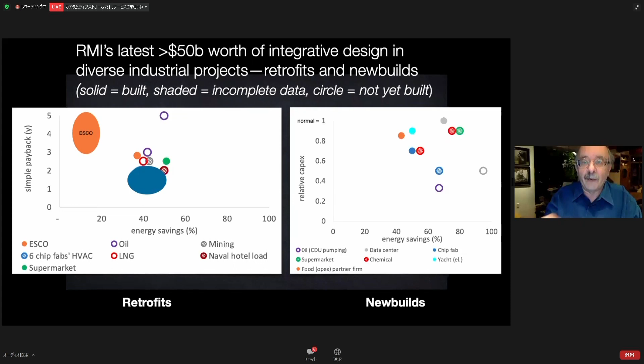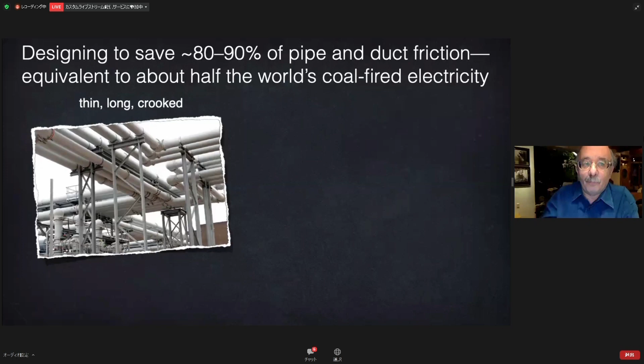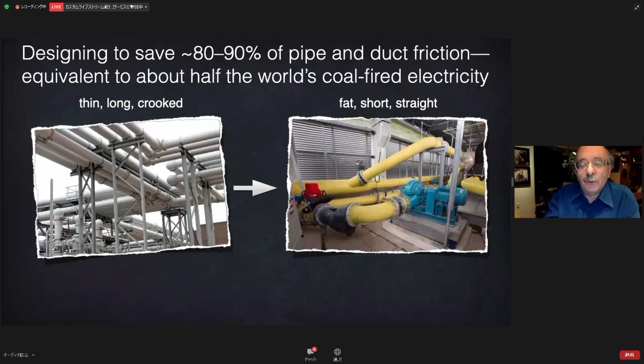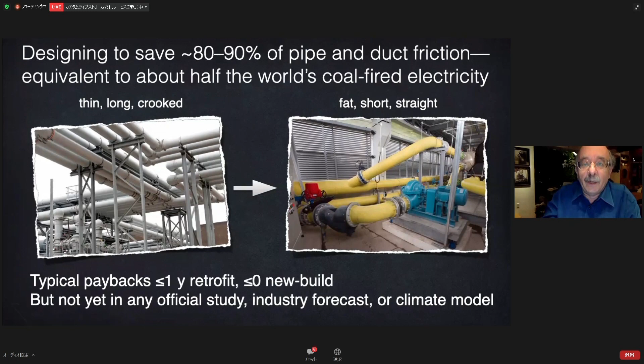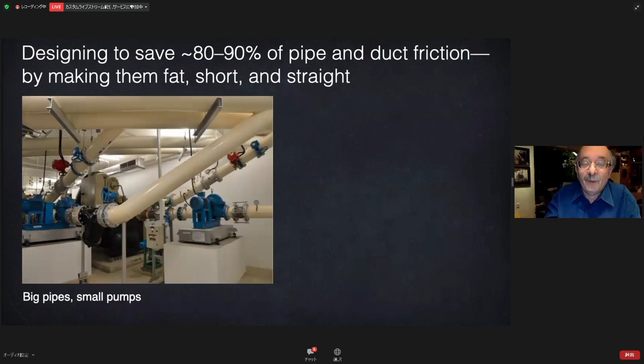Our better systems come from rethinking industrial processes and redesigning basic elements like pump, fan, and motor systems. For example, in both buildings and industry, better pipe and duct design can save about 80 or 90% of friction, 97% here in my house. If everyone did it, this could save roughly two-fifths of the world's electricity, or half the coal-fired electricity, typically paying back in less than a year in industrial retrofits and instantly in new builds. We need simply design big pipes and small pumps, not small pipes and big pumps, and lay out the pipes first, then the equipment.